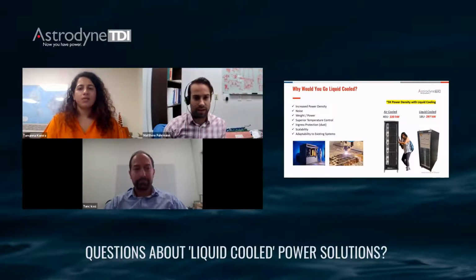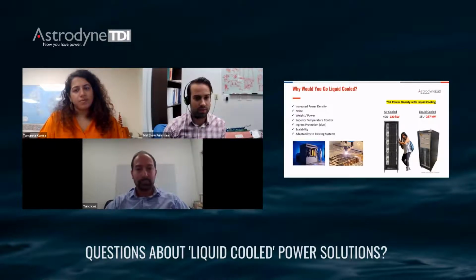With air-cooled power supplies, it's difficult to control where the heat is being ejected. Typically the heat is ejected into the same room as the power supply, out the back, downwind of the fan. Whereas in a water-cooled or liquid-cooled solution, you can choose to exchange the heat in a remote location.